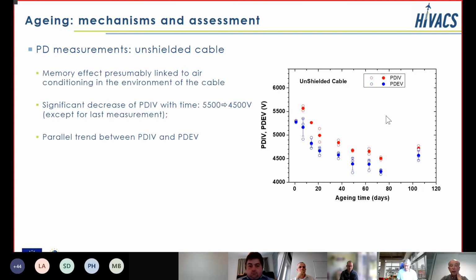In the case of the unshielded cable, we have a much higher inception voltage, beyond 4,000 volts. We have a noticeable drop at the beginning. The inception voltage was about 5,500 volts, it decreased to about 4,500, and then it tends to stabilize. Even the last point here didn't show any more decrease, so that seems to be quite stable.